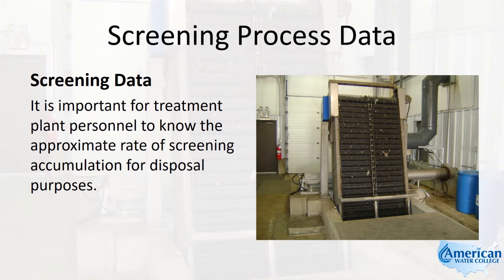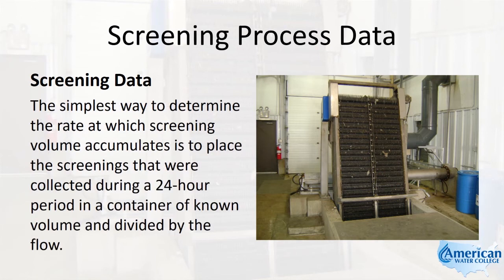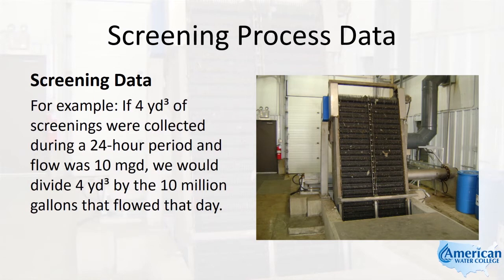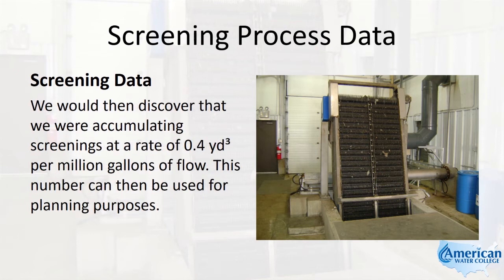It is important for treatment plant personnel to know the approximate rate of screening accumulation for disposal purposes. The simplest way to determine the rate at which screening volume accumulates is to place the screenings collected during a 24-hour period in a container of known volume and divide by the flow. For example, if 4 cubic yards of screenings were collected during a 24-hour period and flow was 10 MGD, we would divide 4 cubic yards by the 10 million gallons that flowed that day, discovering that we were accumulating screenings at a rate of 0.4 cubic yards per million gallons of flow.